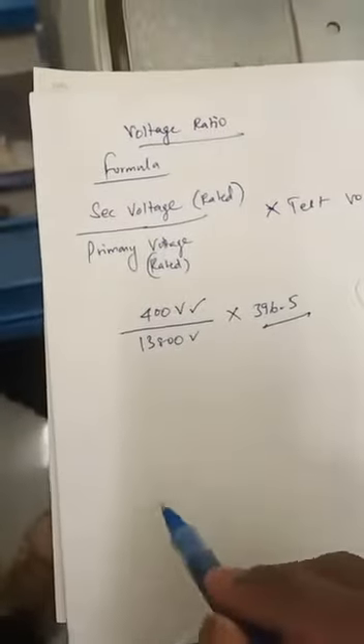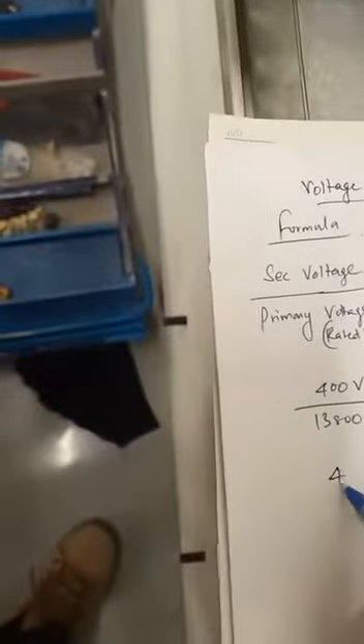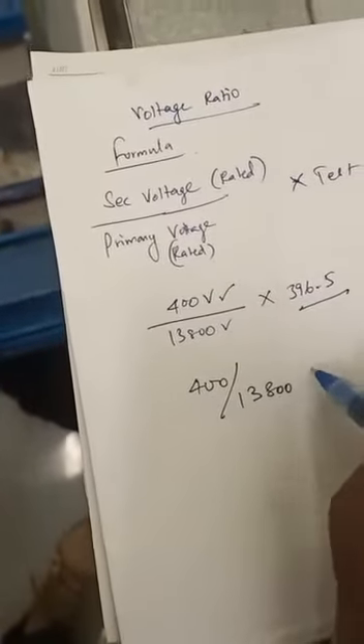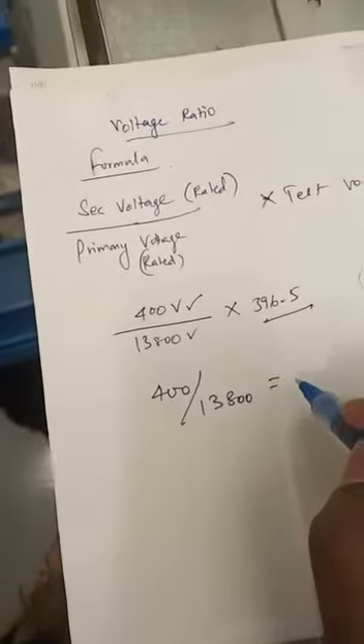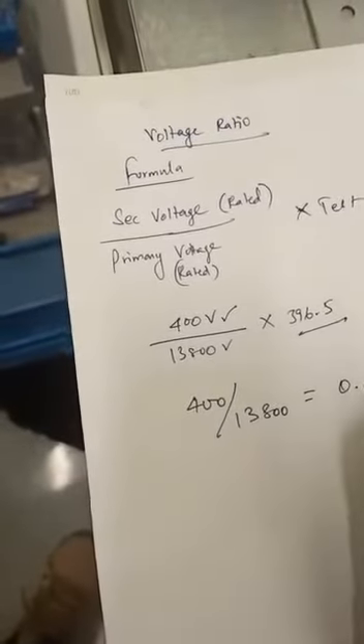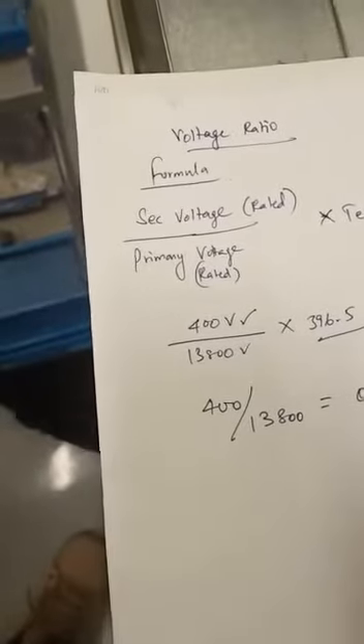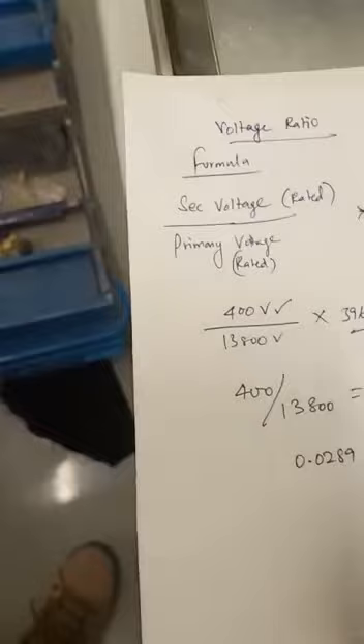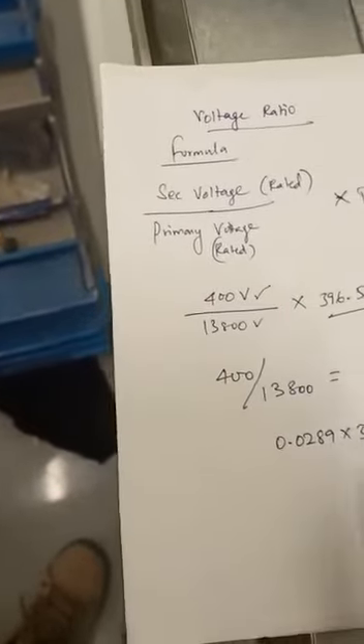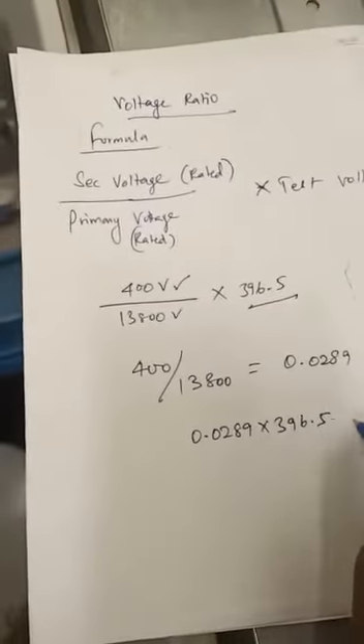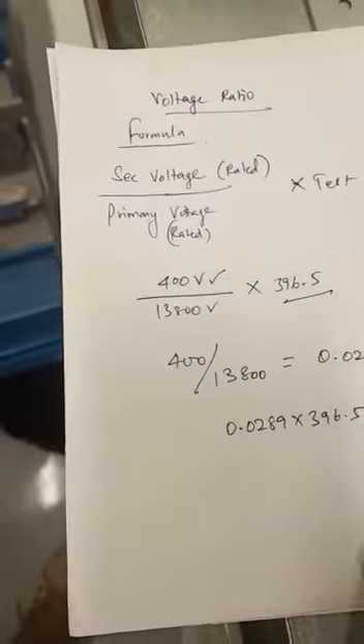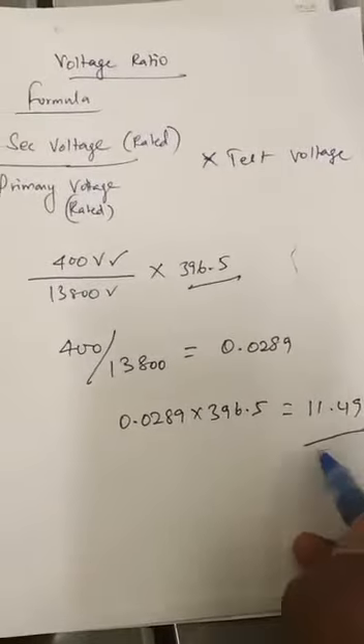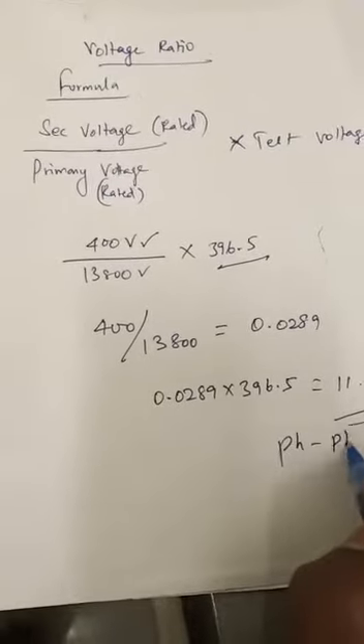So 400 divided by 13800 equals 0.0289, and 0.0289 times 396.5 test voltage equals 11.49. So 11.49 phase to phase you have to get.